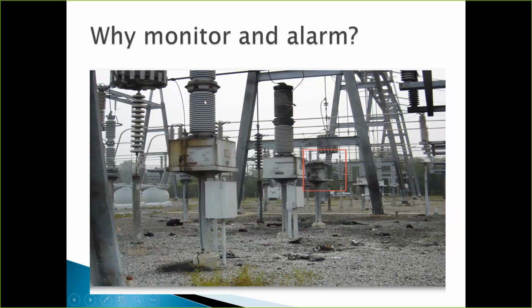It could hit, if there had been a breaker here, it could hit the bushing. You can see the fire it spread out here. It's definitely hazardous to any employee that would have been there in the yard. So the main reason we do this is we want to prevent this. We want to prevent these random end-of-life events and prevent this catastrophic failure is the main reason. It's for our human safety, and it's also to protect the bulk electric system.